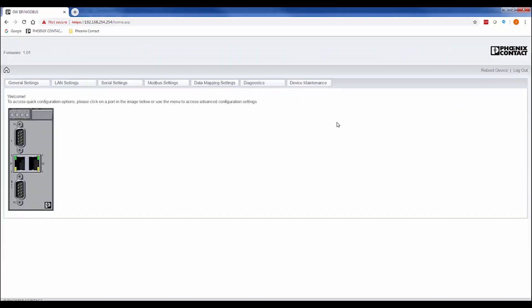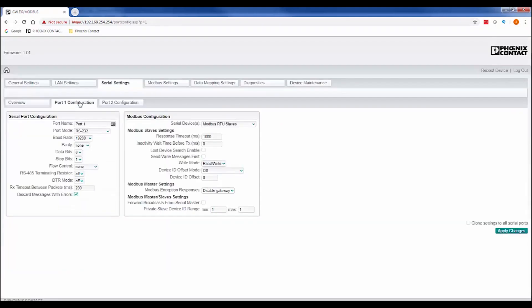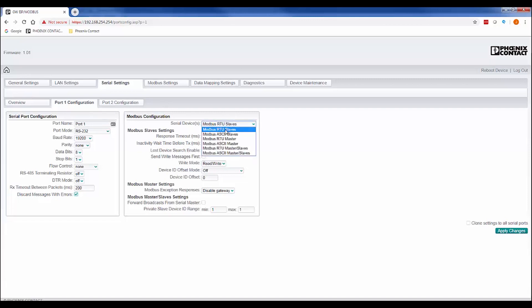Once you are logged in, configure the serial port to match the configuration of the serial device you want to communicate with. To do this, select the serial setting tab, then select the serial port you want to configure. Make sure the serial port configuration matches the communications device you plan on connecting. Verify the setting inside the Modbus configuration field to verify Modbus RTU slaves is selected from the dropdown. You can also modify the response timeout and write mode for the desired communications.